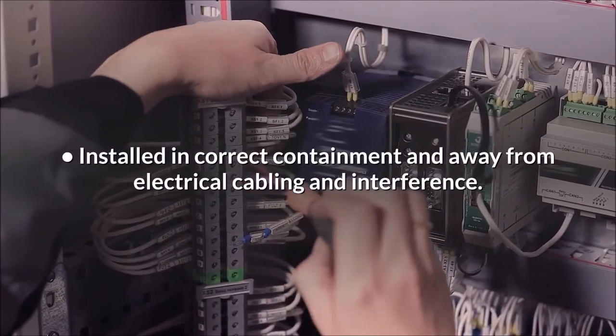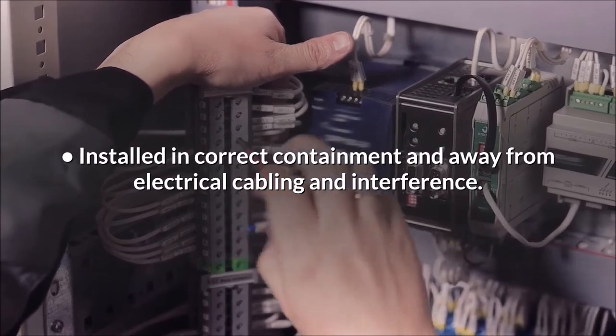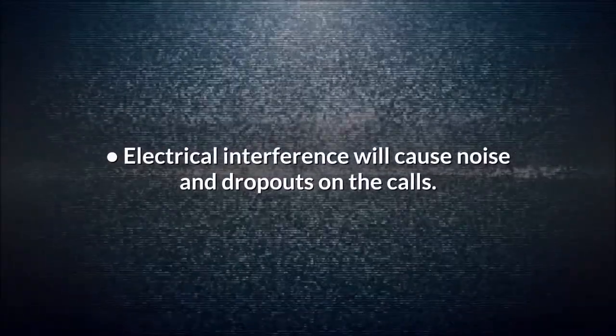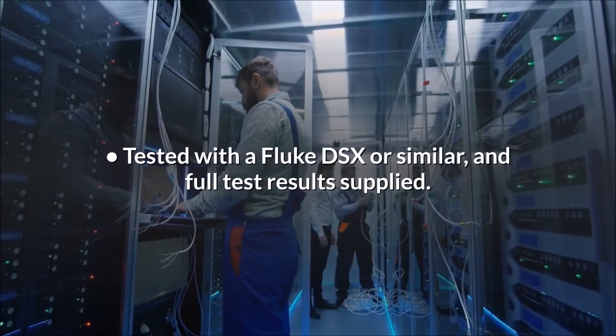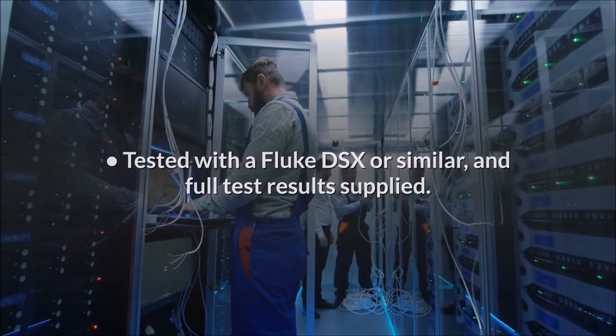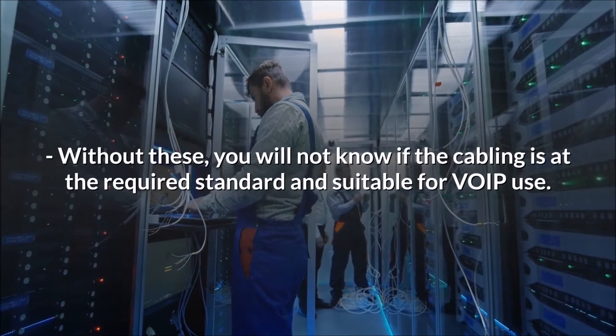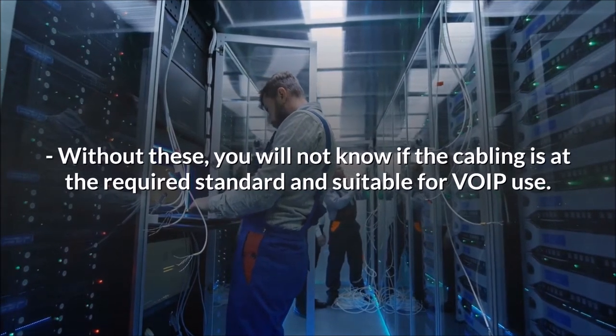Installed in correct containment and away from electrical cabling and interference. Electrical interference will cause noise and dropouts on the calls. Tested with a Fluke DSX or similar, with full test results supplied. Without these, you will not know if the cabling is at the required standard and suitable for VoIP use.